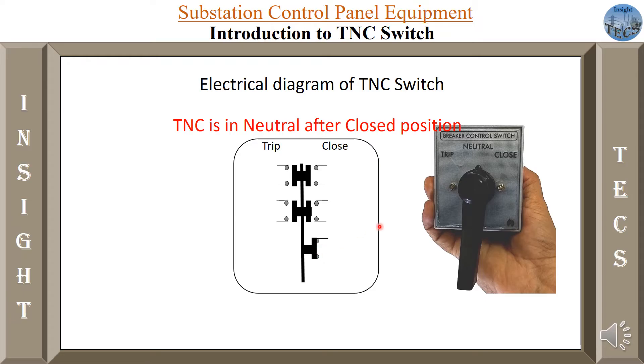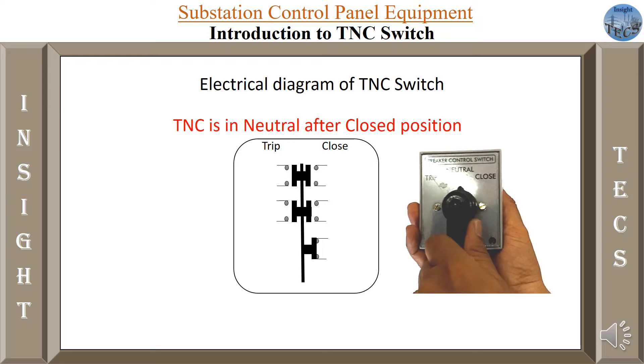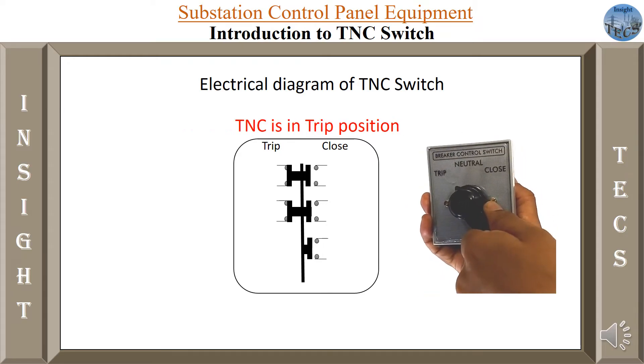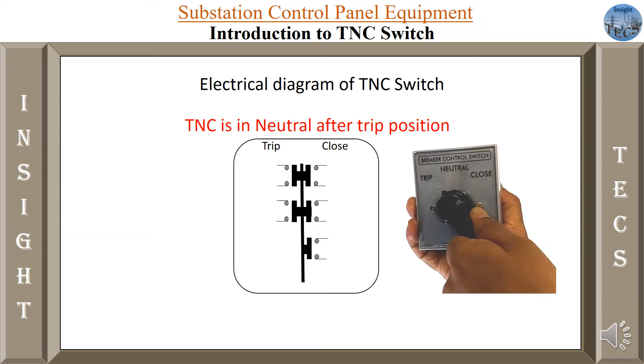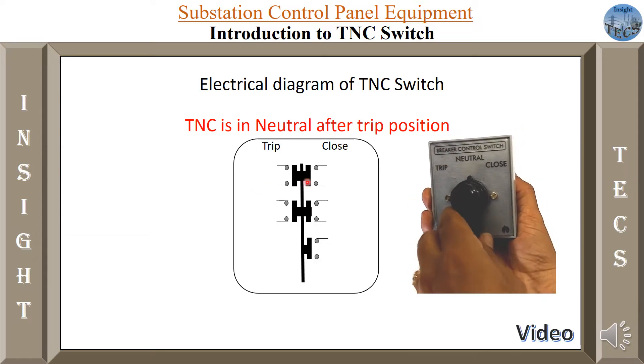Now let us understand what happens when we move the switch towards the trip position. As we move towards the trip side, the contacts move towards trip position. This NO now becomes NC — it is closed. But observe that the auto-reclose contact is now open when we have moved the switch towards the trip position. When we bring the switch back to neutral, the contacts are again normally open, and this auto-reclose contact also remains NO.